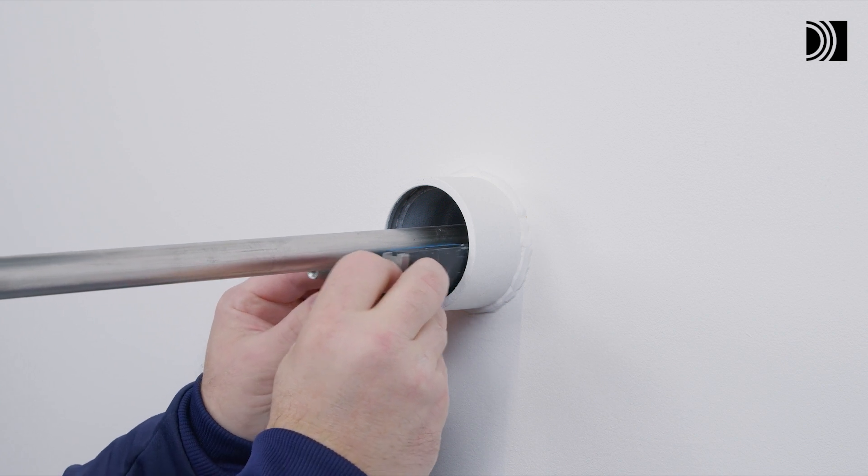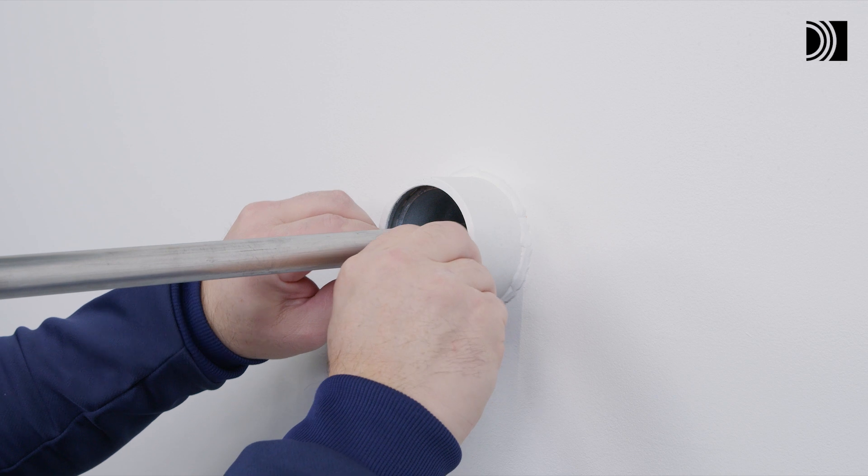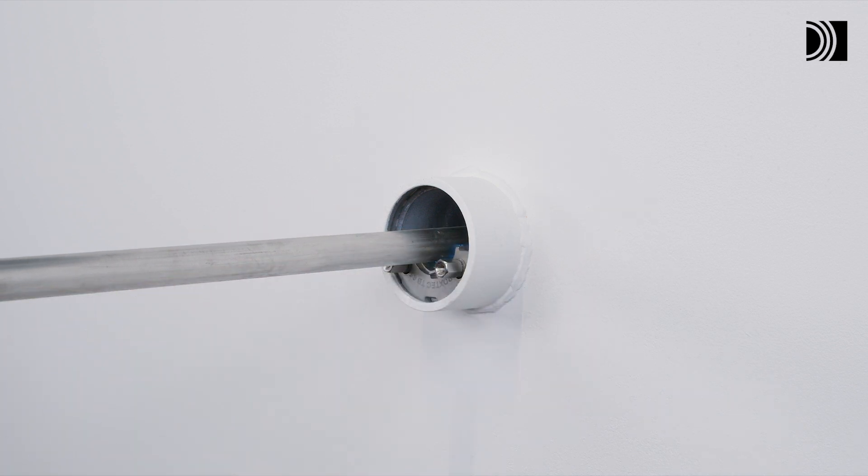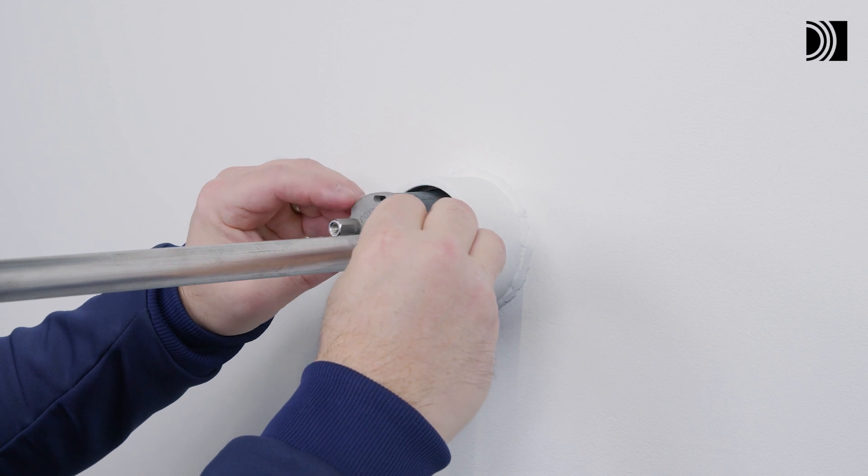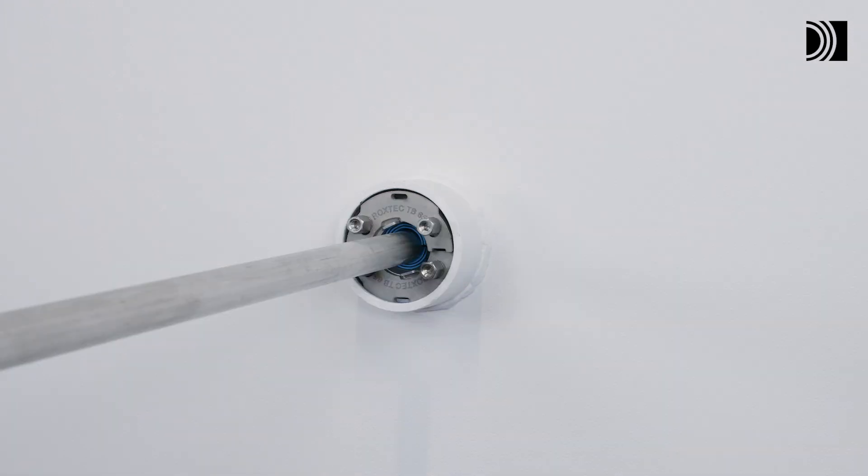Install the seal. Insert the first half into the sleeve. Make sure the front fitting is as far into the groove as possible. Insert the second seal half into the sleeve. On the second seal half, press the front fitting as far towards the center as possible.